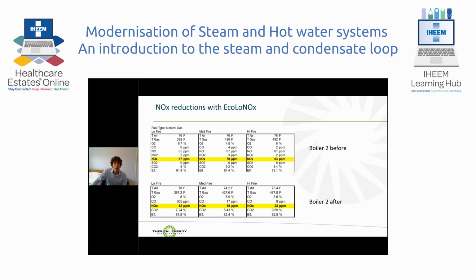Here are the results in terms of the NOx emissions on boiler 2. You can see that the NOx emissions depend on whether you're at low fire, medium fire or high fire. And across all of those conditions, there's a significant reduction in NOx emissions, from around 63 parts per million to 70 parts per million prior to the EcoLoNOx being installed. Following the installation of the EcoLoNOx, they vary from 12 parts per million to 22 parts per million. Overall, this is a reduction in NOx emissions of 74%.